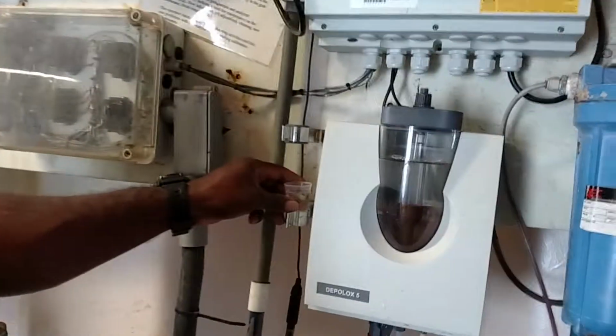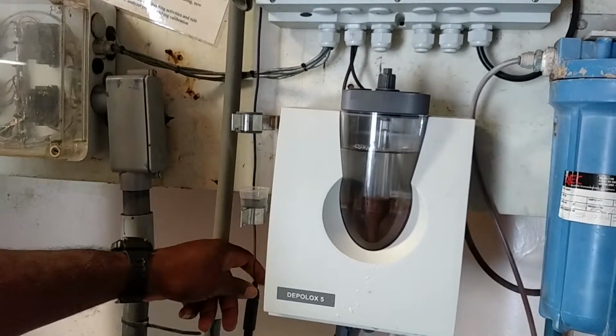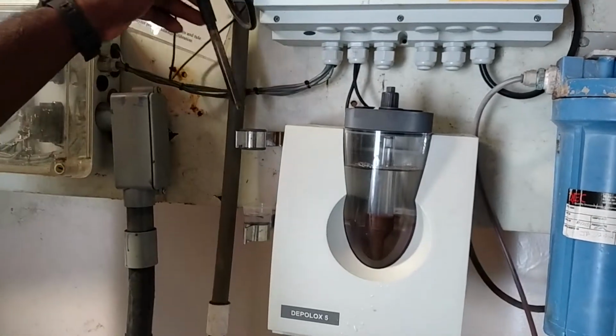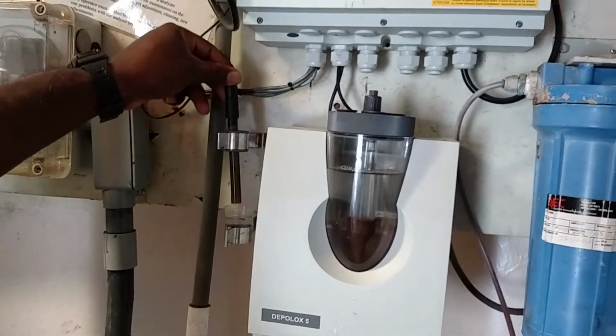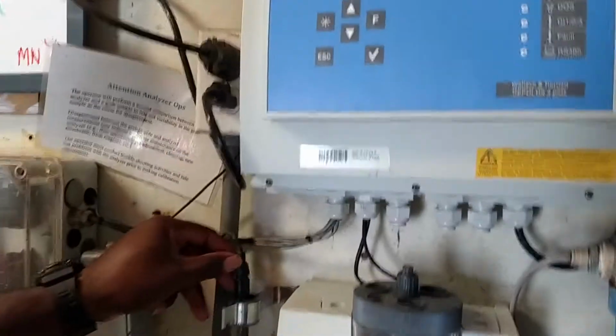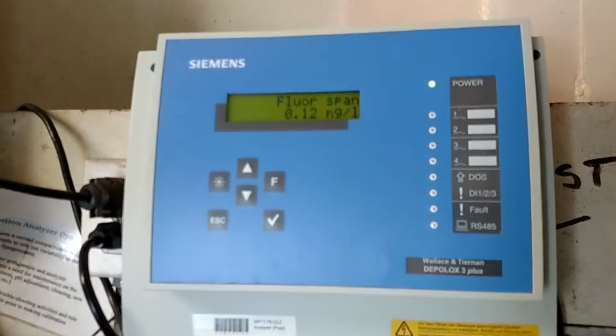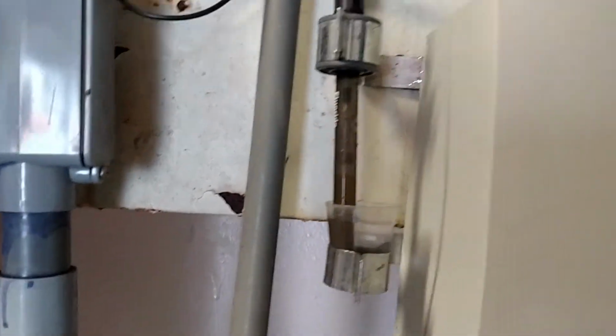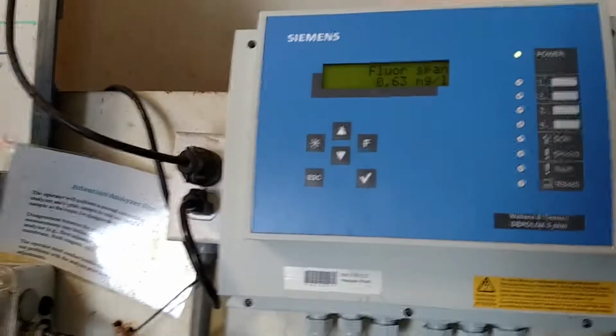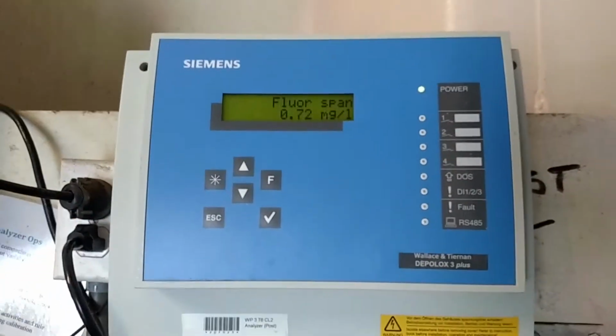So now I already rinsed my probe off. I got my 2.0 standard in. I just set the probe in there. And one of the things is to try not to touch the bottom of the probe, or the sensor of the probe itself, with your hand. With your hand? Yes. So you can see the alarm light has gone off for now.